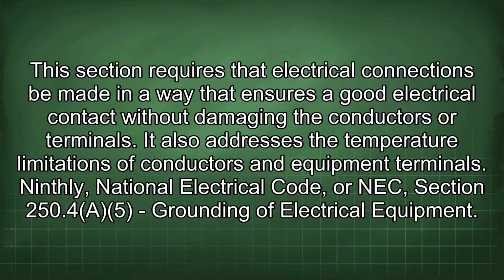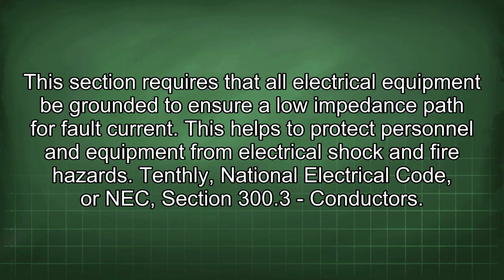Ninthly, NEC Section 250.4(A)(5) Grounding of electrical equipment. This section requires that all electrical equipment be grounded to ensure a low impedance path for fault current. This helps to protect personnel and equipment from electrical shock and fire hazards.